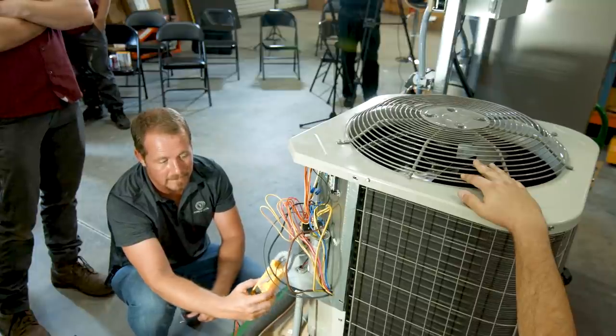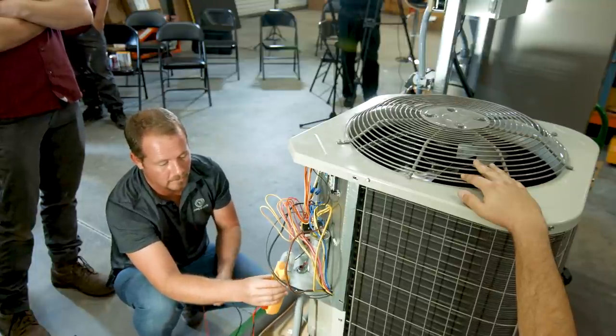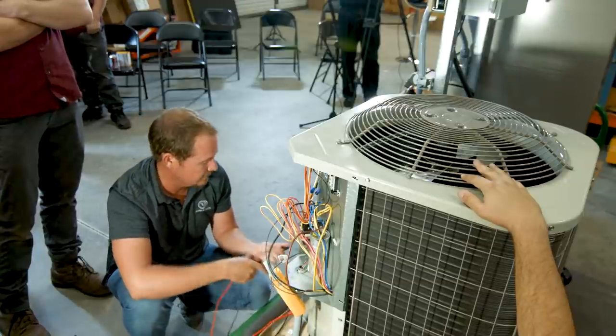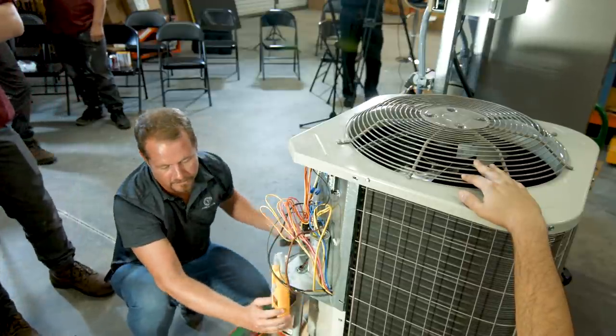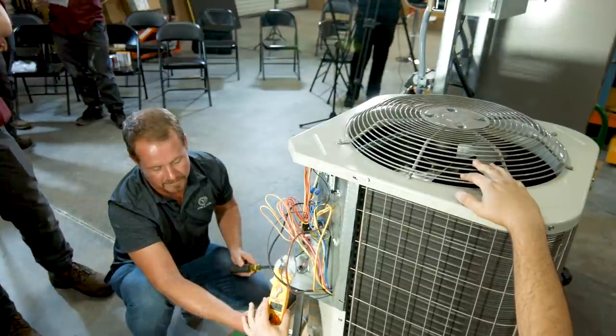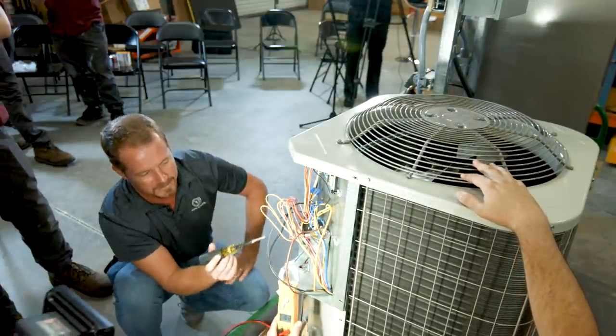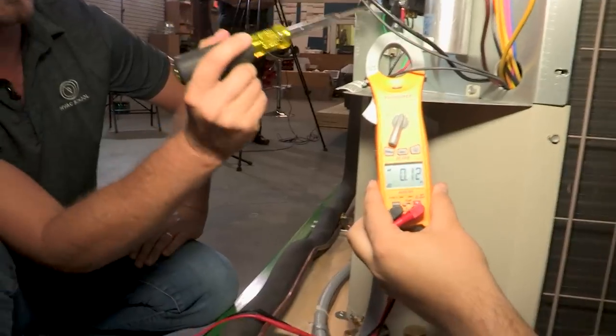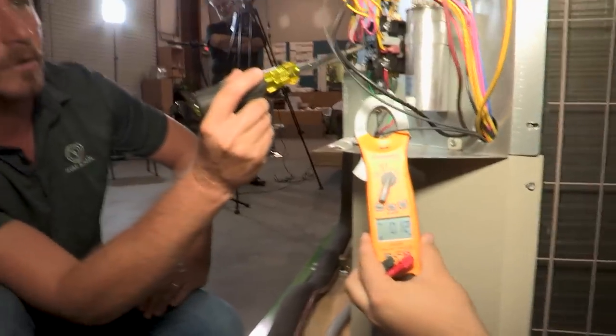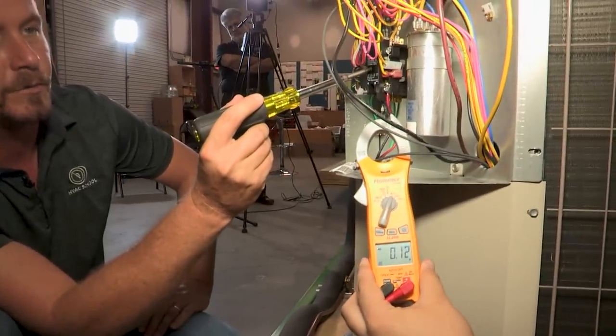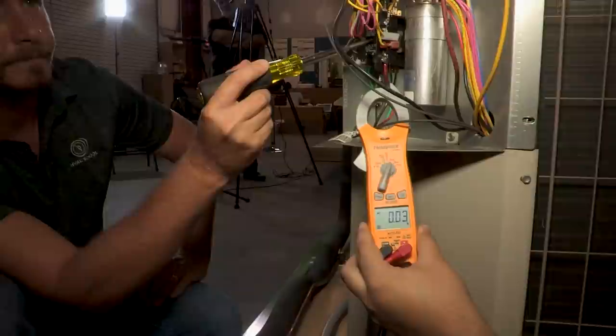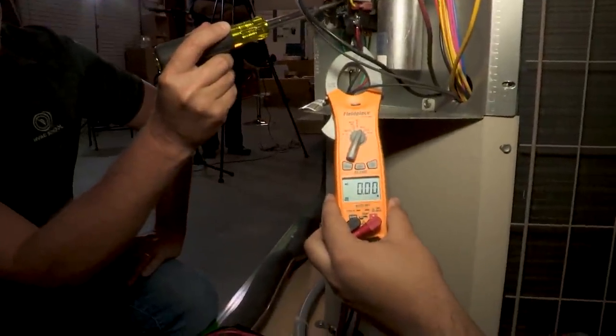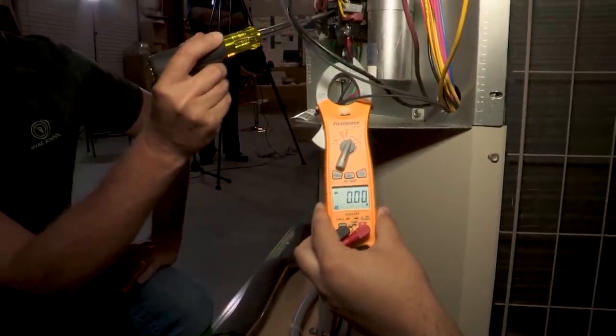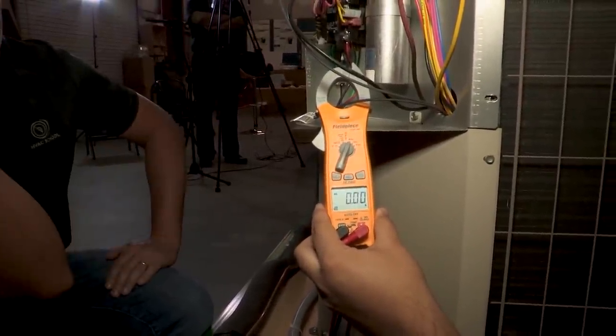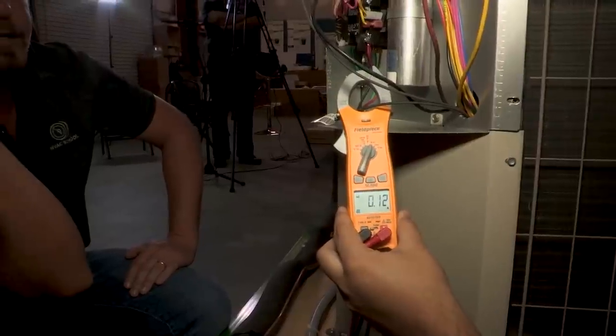That's it. Now, as soon as we energize, and I'll go ahead and do it just by pushing it in. But I want you to hold this here so you and the camera can see it. As soon as we energize it, now there is no potential across this any longer because electrically those two points become the same. Zero. So when it's running, it's not heating the compressor. When it's not running, it is heating the compressor.